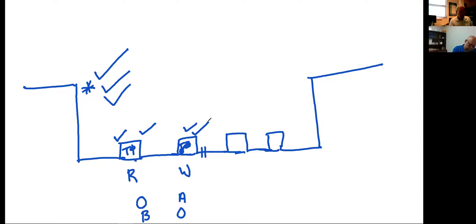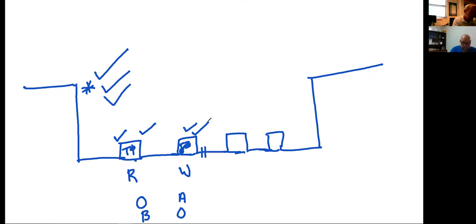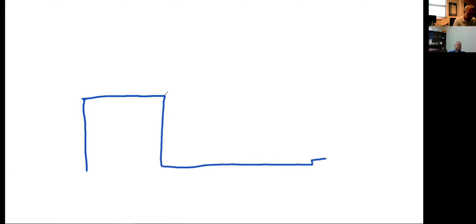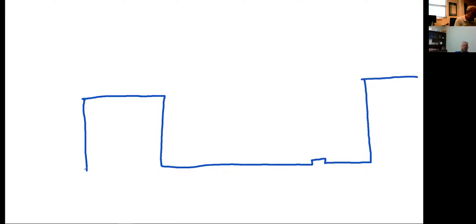Any questions about fault indicators — their purpose, how they're used? Remember, there are multiple types out there. Robbie, have you seen any overhead indicators? Yes — I had many of them in my area because I had a lot of rural territory, and I strategically placed them on the three-phase so I could know how far down to look from a fault. Very, very good piece of equipment for overhead as well.